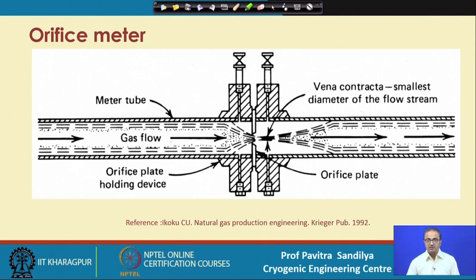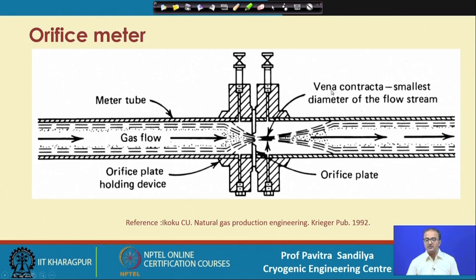This beveling is done to slowly expand the gas, because if the edge is very sharp there will be a lot of energy loss. To reduce the energy loss we make it a bevel edge. The flow converges at the orifice and then slowly starts expanding again, occupying the whole pipe. The minimum area attained by the stream is called the vena contracta, which gives the smallest diameter of the flow stream.